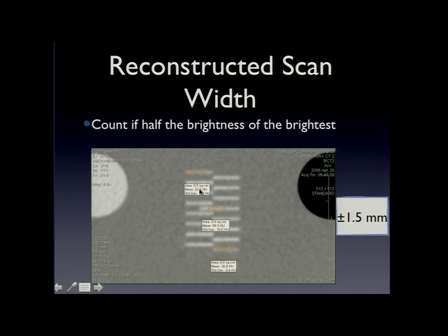So that will help you to verify that. As an example, you can put a region of interest over the rod, and if you have doubt, because a lot of times you can do it by eye, just subjectively, and count it that way. But if you're concerned, particularly if you acquire them using a helical acquisition, they get distorted and they're really difficult to look at. If you want to really confirm the full width half max of these test objects, you can put a region of interest on there and actually measure the CT number and filter out which ones you really don't need to count.